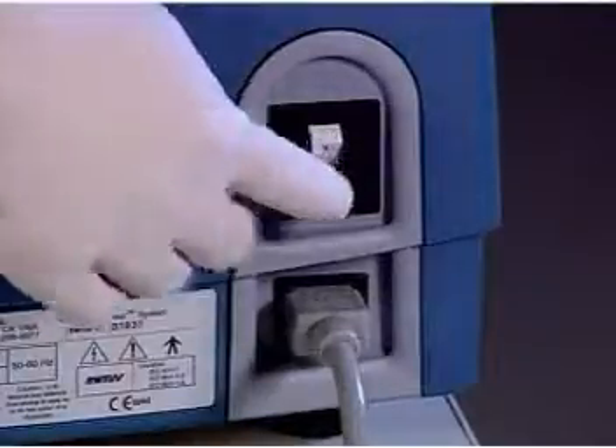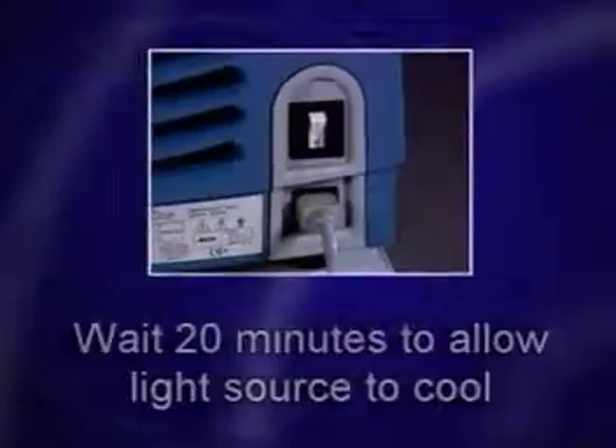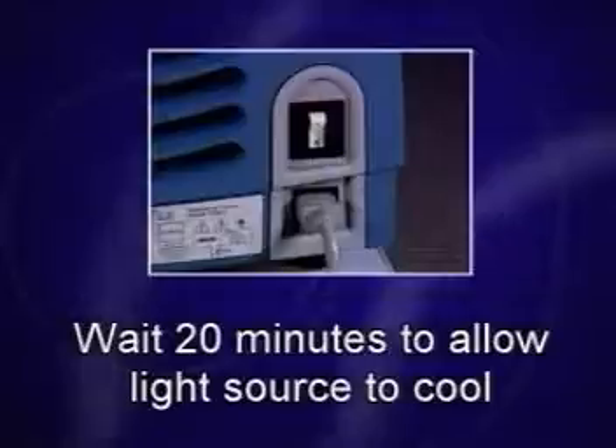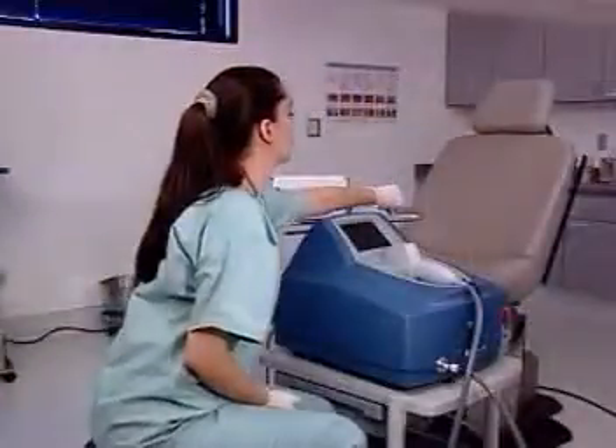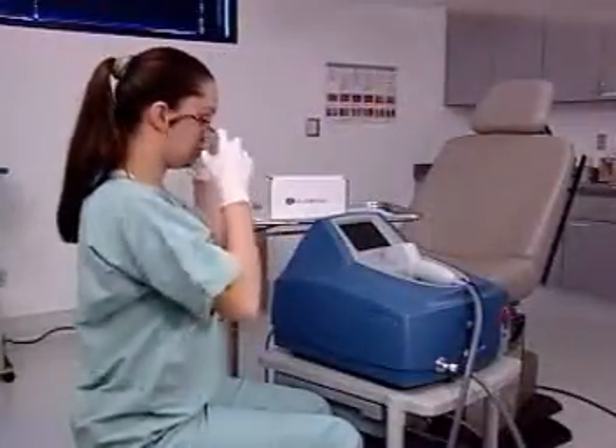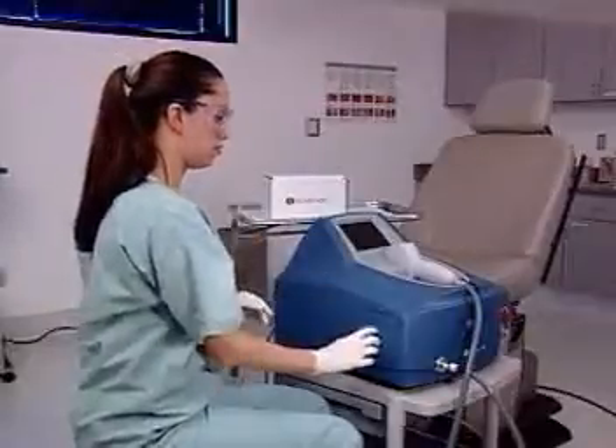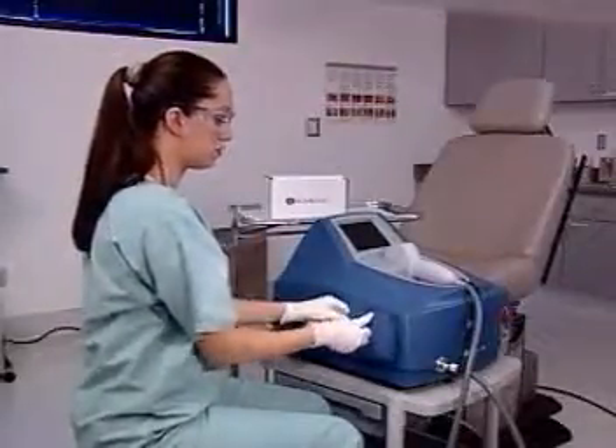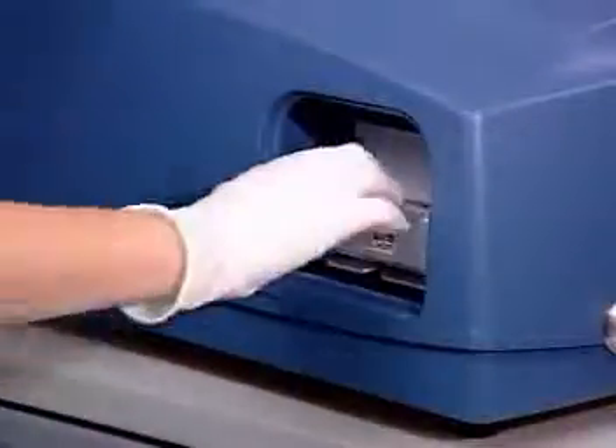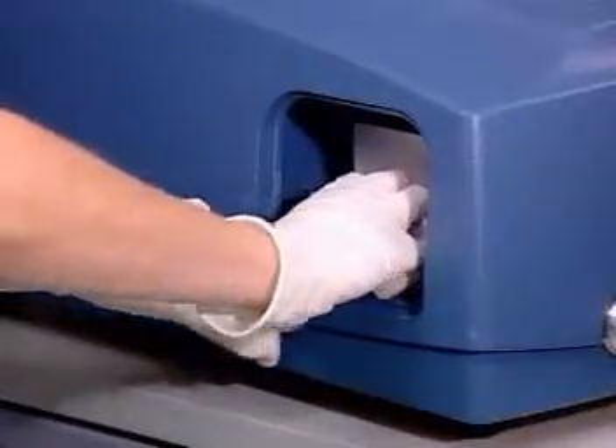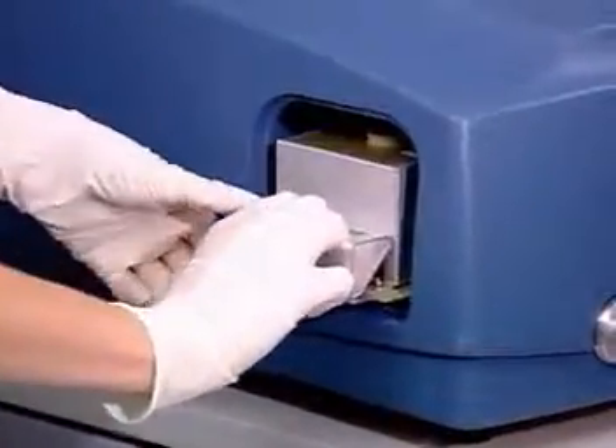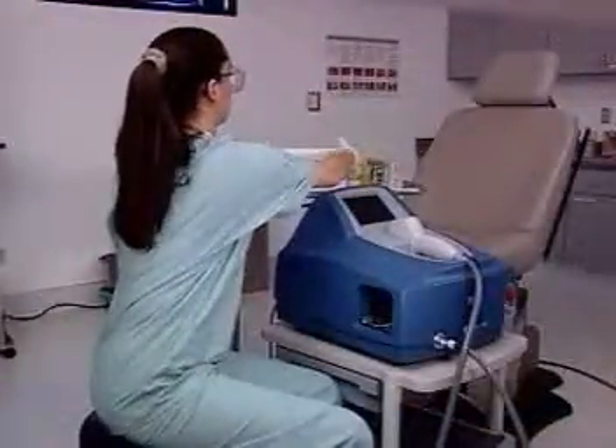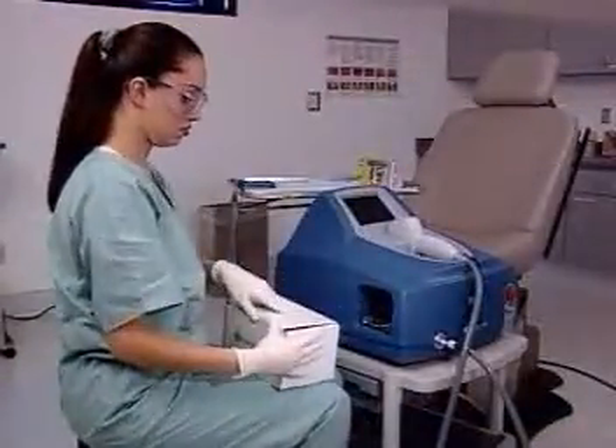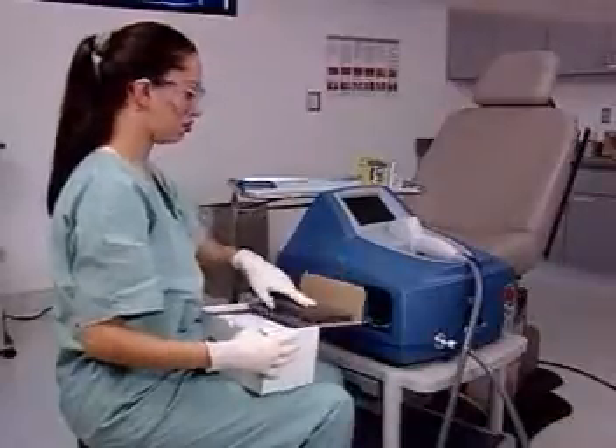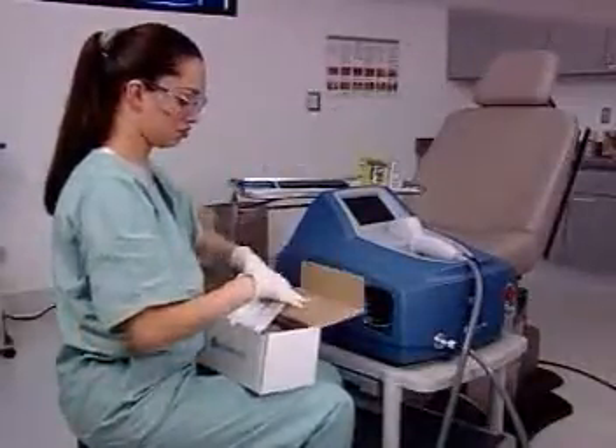Shut down the system before replacing the light source. Wait 20 minutes to allow the light source to cool. Put on gloves and safety glasses. Remove the exterior door. Grasp the handle on the light source assembly and carefully pull it out. Place the used light source on its side on a flat surface. The light source contains mercury vapor and should be handled carefully.